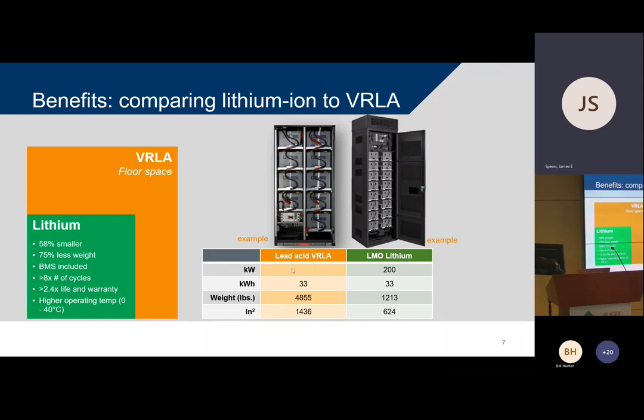It's also much lighter. In the table at the bottom, the kilowatt hours are both 33, about the same backup time. The traditional battery weighs 4,800 pounds, while the lithium battery weighs 1,100 to 1,200 pounds for the same backup time. The footprint is about 38 inches wide by 42 inches deep for the lead battery, versus about 24 by 24 inches for the lithium battery. Notice the lithium battery is significantly taller than the other cabinet and most UPS systems, since these vendors designed with a definite fixation on footprint.